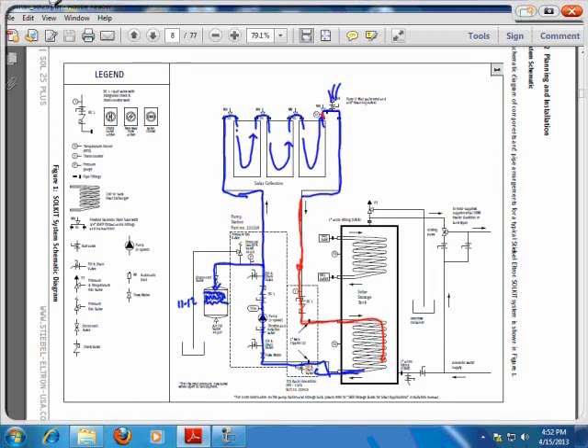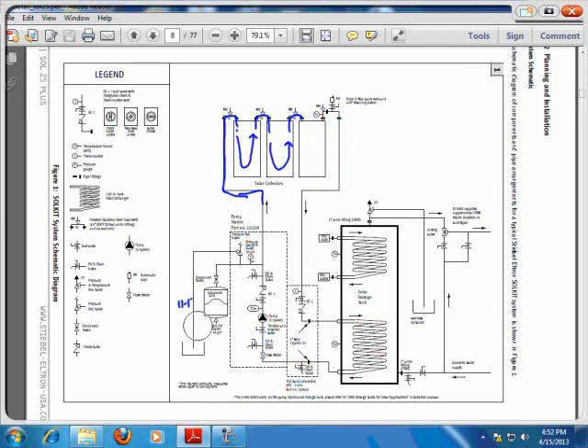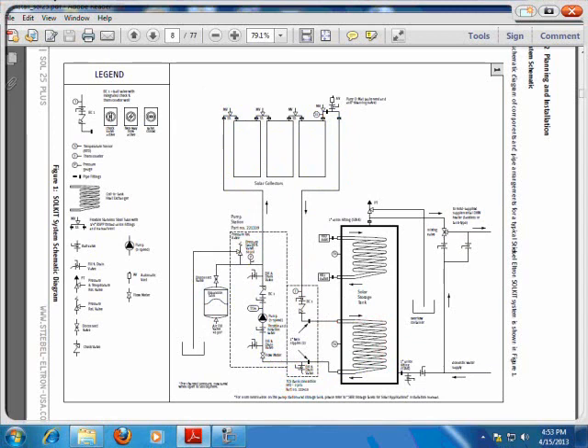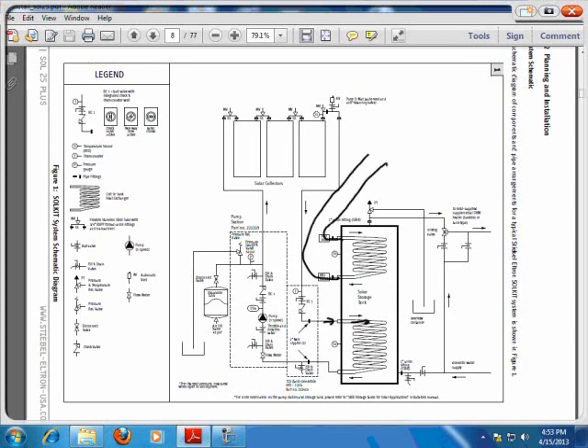The rest of this is some manifolds that we're going to look at in the tank. When you deal with municipal water supplies or any time there is potable water, and potable water means water that you can drink, you always have to have a double isolation from it, so that should be a double line. So the glycol system comes into this loop that's closed. The hot water that you would run into your hot water tank comes from this upper loop. That means there are two physical barriers that is going to keep that propylene glycol out of our drinking water, and that would be these two coils. So that's a double wall.